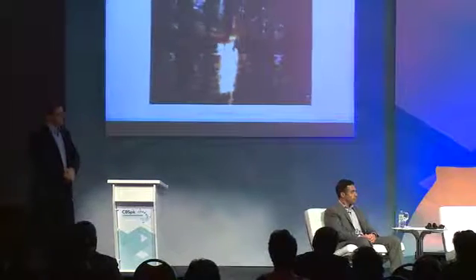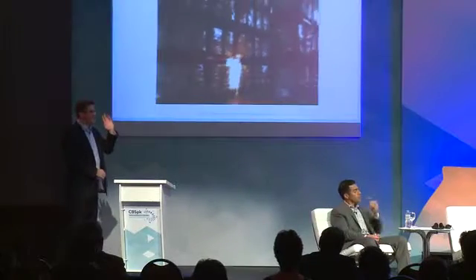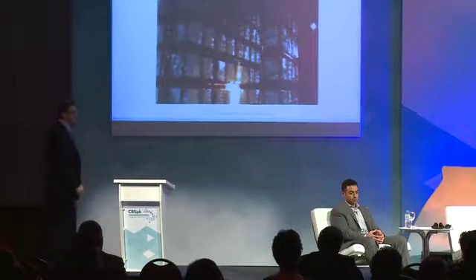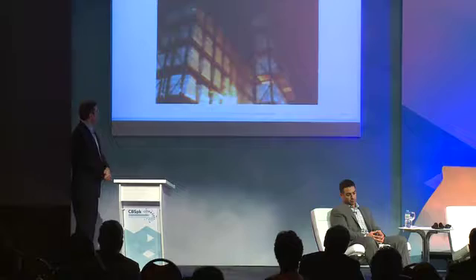These tests, and we ran a lot of them with the foundation, these tests all look about the same. Flame spreads up the rack, takes 45 seconds to get up to the ceiling or so. This one's going to be stopped a little bit by that horizontal barrier. You'll notice it when the sprinkler operates in the rack because that fire gets knocked down. So it hit the barrier right there, and in just a second here you'll see the sprinkler operate and you'll see the fire come back down to the floor.